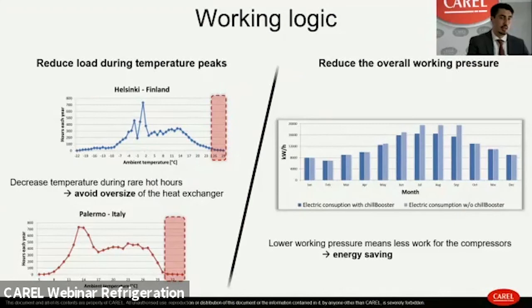So talking about the logic, there are two main options that can be pursued with the chillBooster. Both are in the direction of energy efficiency and efficacy. In the option on the left, you see that the chillBooster is responsible to avoid the summer heat peaks. For a very small amount of hours during the year, some heat peaks happen, and they are kind of an extreme condition considering the normal profile and the standard profile of the temperature distribution. In this case, it would be quite a waste to dimension the gas cooler for such a rare condition. chillBooster comes to help in these cases to just cut this unusual temperature and let the end user size the gas cooler for a more standard condition.